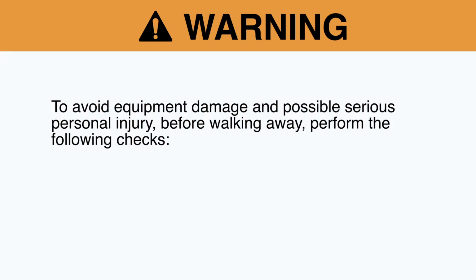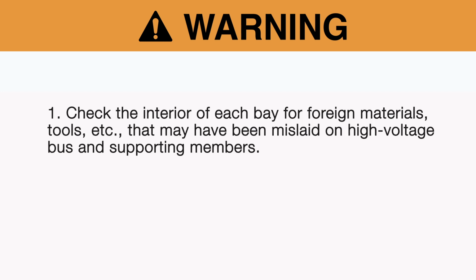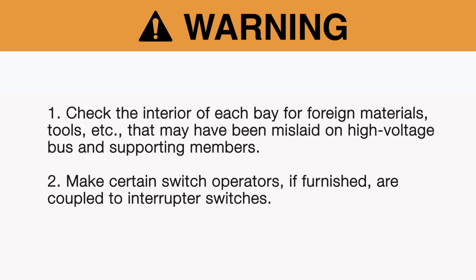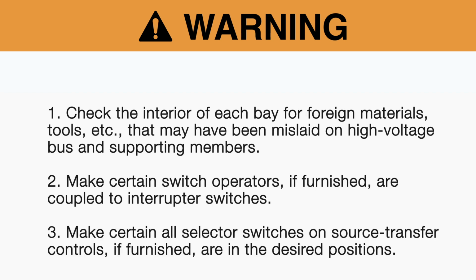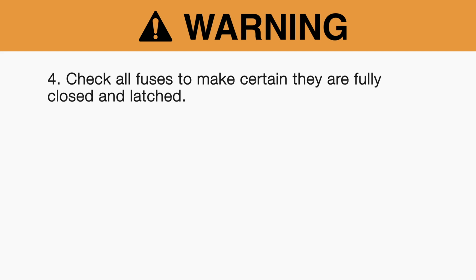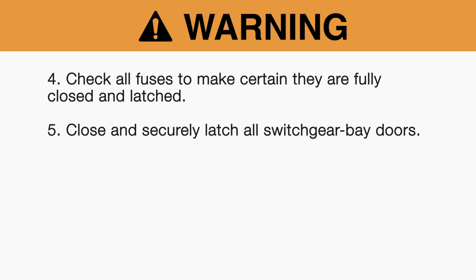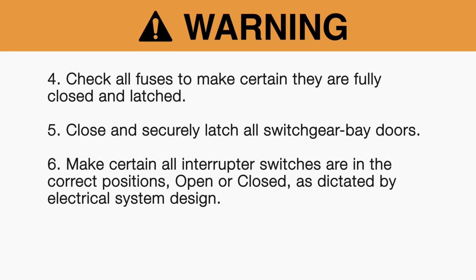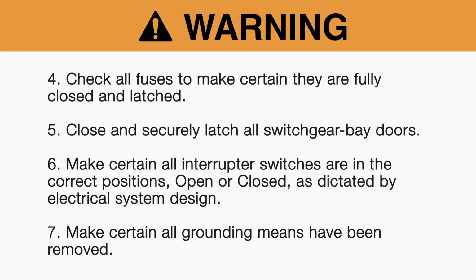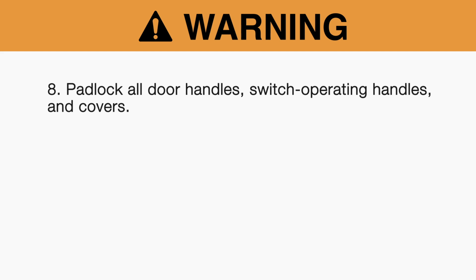Warning: to avoid equipment damage and possible serious personal injury, before walking away, perform the following checks. 1. Check the interior of each bay for foreign materials, tools, etc. that may have been mislaid on high-voltage bus and supporting members. 2. Make certain switch operators, if furnished, are coupled to interrupter switches. 3. Make certain all selector switches on source transfer controls, if furnished, are in the desired positions. 4. Check all fuses to make certain they are fully closed and latched. 5. Close and securely latch all switchgear bay doors. 6. Make certain all interrupter switches are in the correct positions, open or closed, as dictated by electrical system design. 7. Make certain all grounding means have been removed. 8. Padlock all door handles, switch operating handles, and covers.